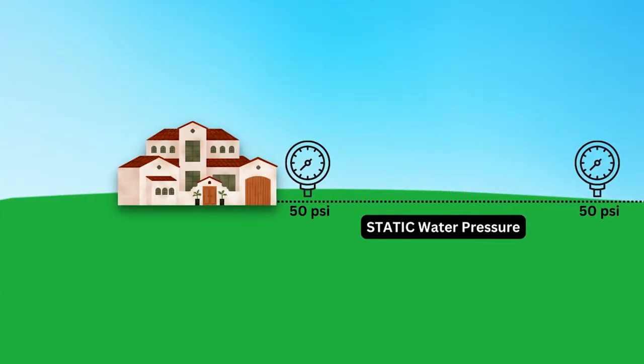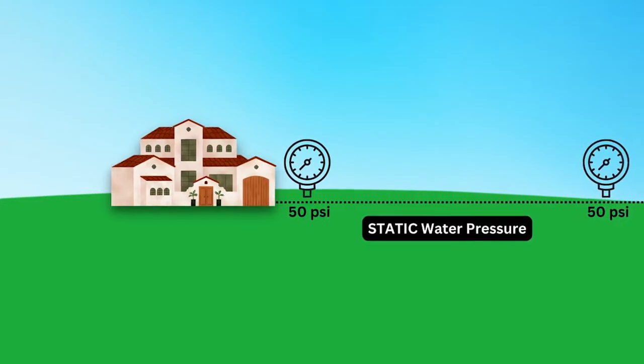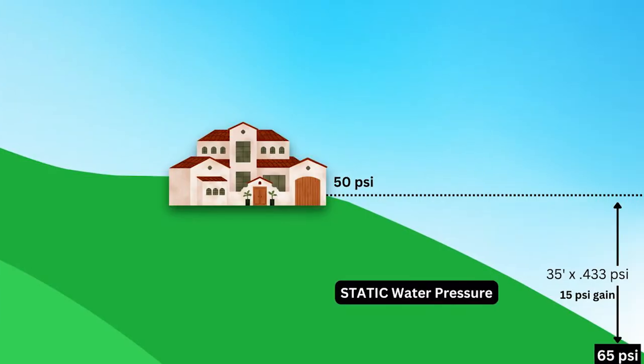Static water pressure is the pressure when the water is motionless. In a level piping system, static water pressure is the same everywhere — it is the same at the beginning of the system and at the end of the system. The only difference in pressure is going to be elevation. Water at the top of a hill will be at a lower pressure than water at the bottom of the hill because the force of gravity on the water is what changes static pressure.